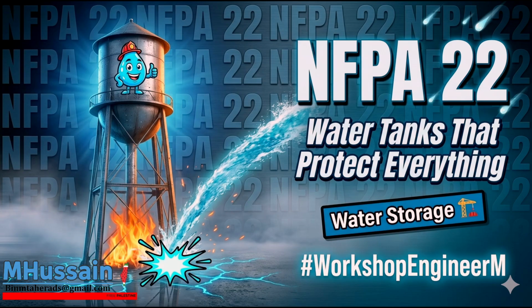Precisely, which is why the NFPA completely rewrote several critical rules in the 2023 edition of NFPA 22. Yeah, the standard for water tanks for private fire protection. And today, this deep dive is custom tailored for you, the safety engineer. We're going to strip away the dense regulatory jargon. Exactly. We want to look at the raw physics of why these water systems fail and how to engineer them correctly. We're exploring the fluid dynamics, the thermodynamic load limits, and the specific mechanical failsafes. The things that make these regulations absolutely necessary for your daily design work. We are pulling actionable design principles directly from the official 2023 text.